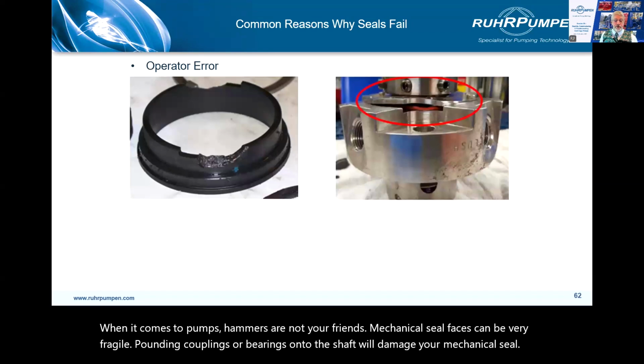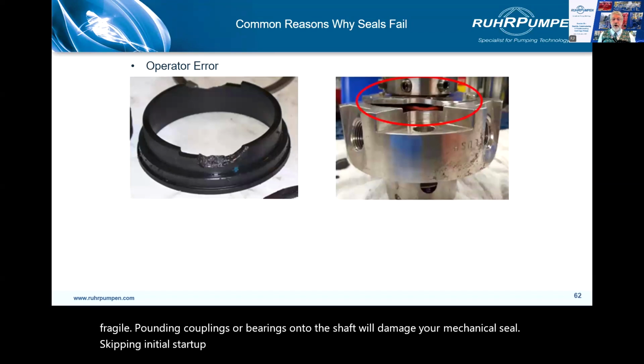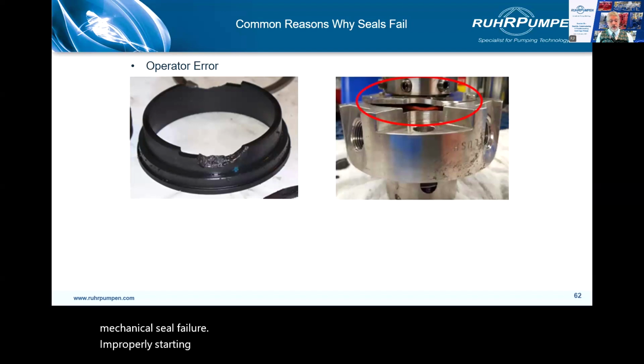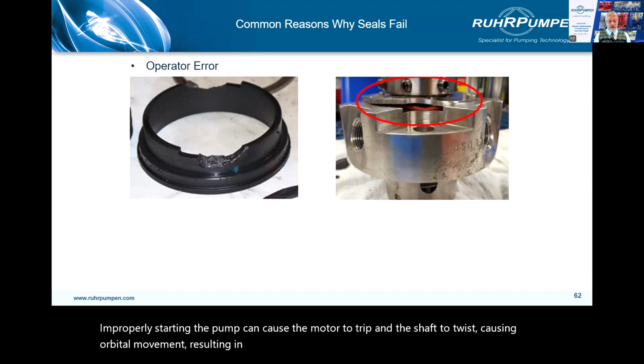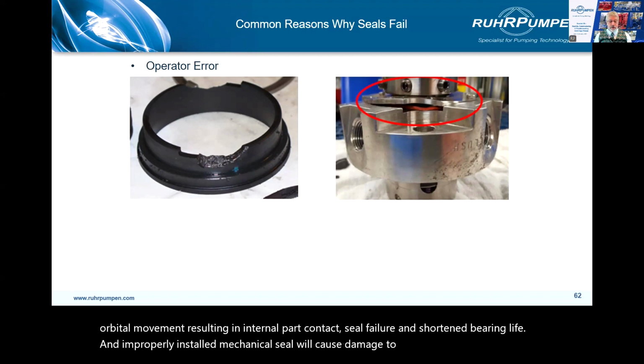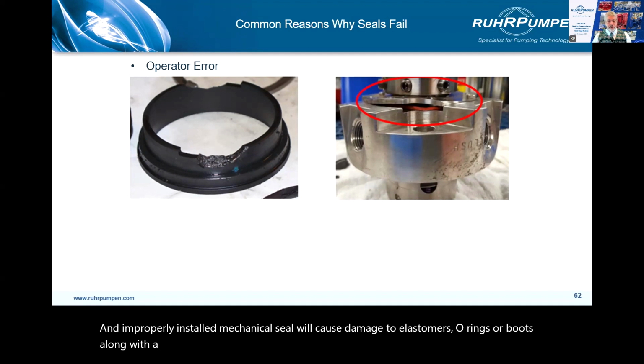Skipping initial startup procedures and installation errors are a big factor when it comes to mechanical seal failure. Improperly starting the pump can cause the motor to trip and the shaft to twist, causing orbital movement, resulting in internal part contact, seal failure, and shortened bearing life. An improperly installed mechanical seal will cause damage to elastomers, O-rings or boots, along with a wide variety of other issues, as pictured here to the left.